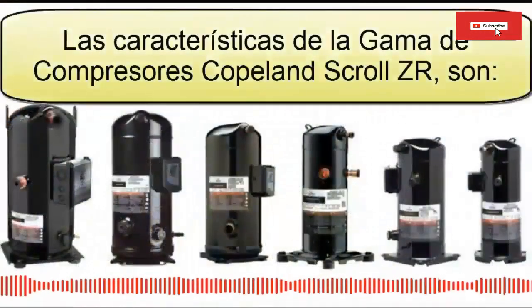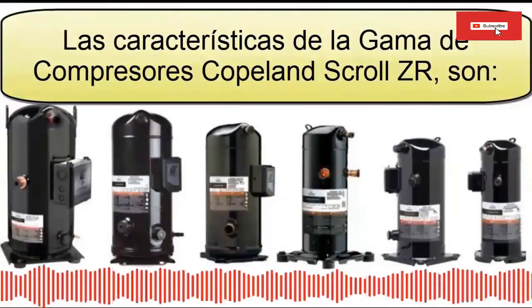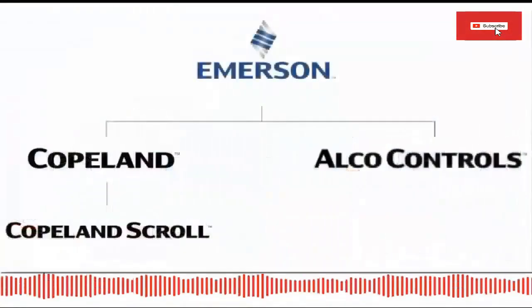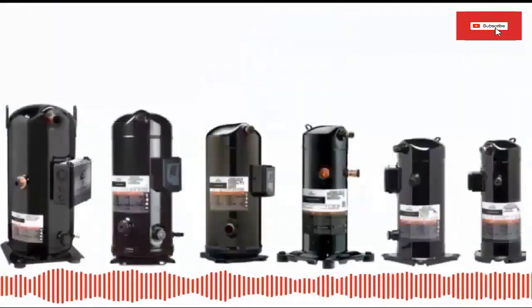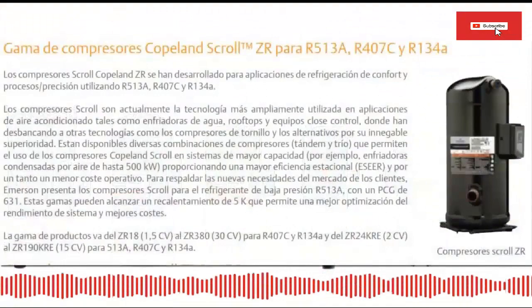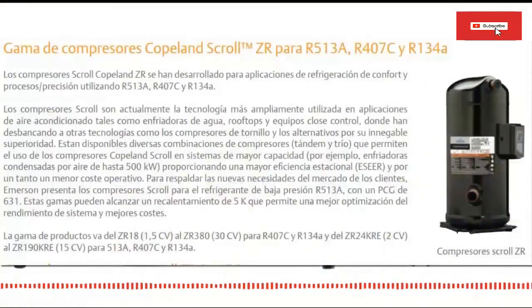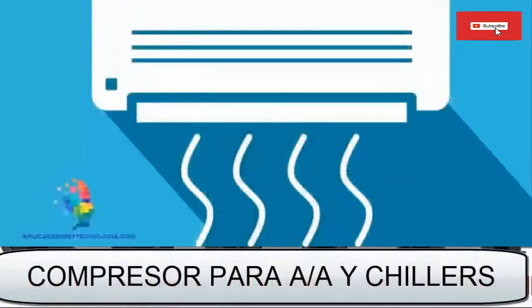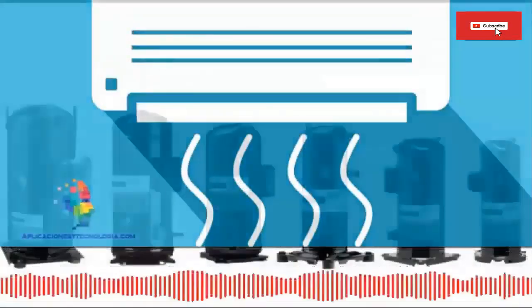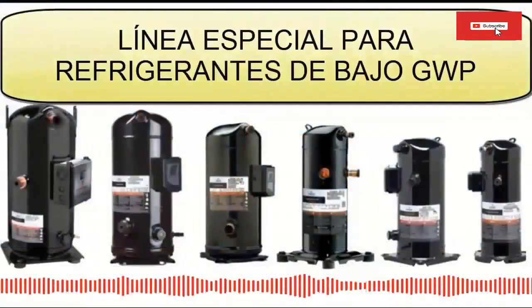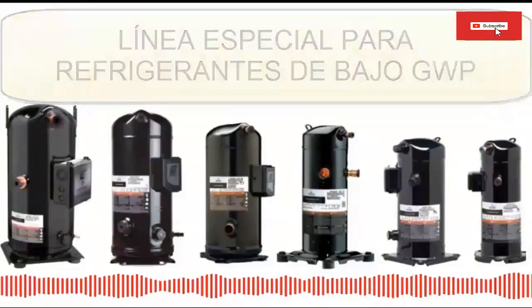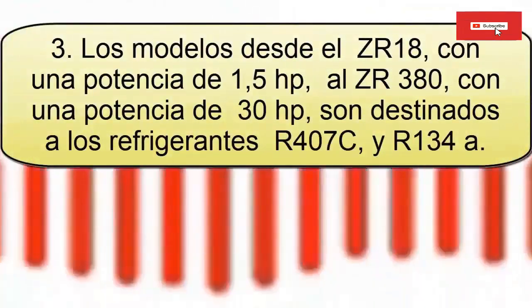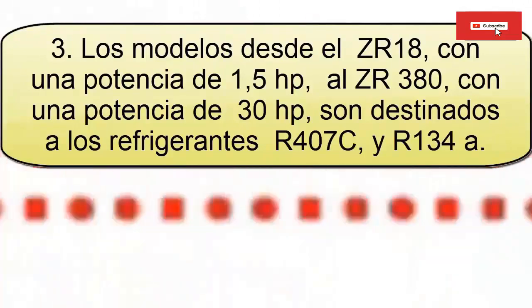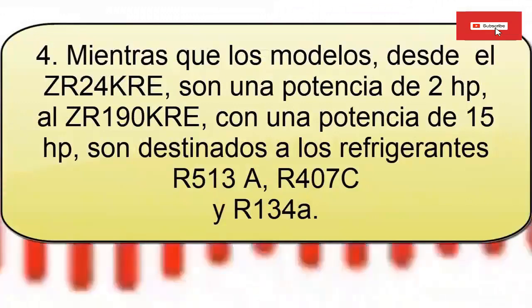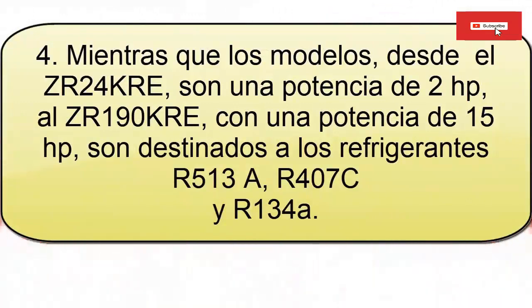The characteristics of the range of Copeland scroll ZR compressors are: 1. Scroll Copeland ZR compressors have been developed for precision process and room air conditioning applications using R513a, R407c and R134a refrigerants. 2. Although R407c, R134a and R513a have different compressor saturation and discharge pressures, the design of this line of compressors allows the use of these refrigerants. 3. The models from the ZR18, with a power of 1.5 HP, to the ZR380, with a power of 30 HP, are intended for refrigerants R513a, R407c and R134a.